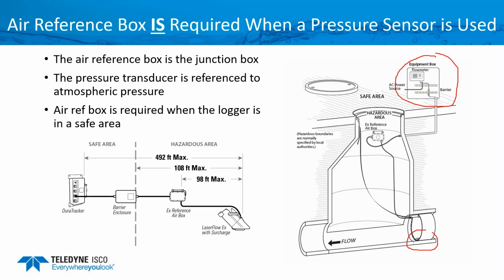Now, over here on the left side, if we're still going to use the air reference box, the laser flow sensor by itself doesn't have a pressure transducer, but in this case, we have a surcharge sensor on the bottom, which needs to reference atmospheric pressure. Once we're out of the hazardous area, the IS barrier is required to connect to your logger or flow meter.